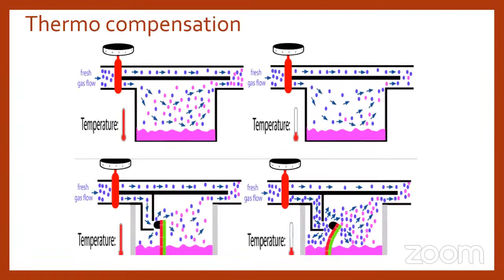And coming to thermal compensation, as I've already discussed, when the liquid converts into vapor, it loses heat. So when the liquid loses its heat, the next round of vaporization will be reduced. To avoid this temperature effect on liquid vaporization, we have incorporated a system, as you can see in the bottom picture. It has a temperature control rod equipped with a block to minimize or maximize the flow of fresh gas into the vaporizing chamber.